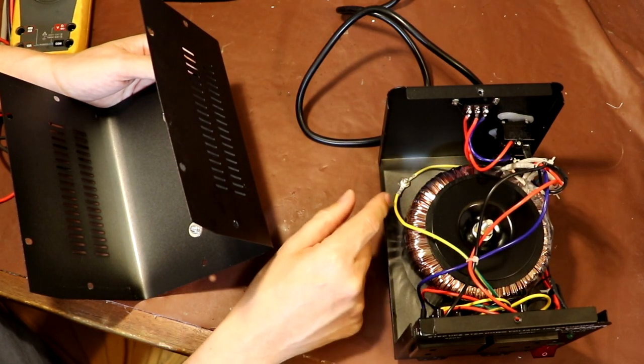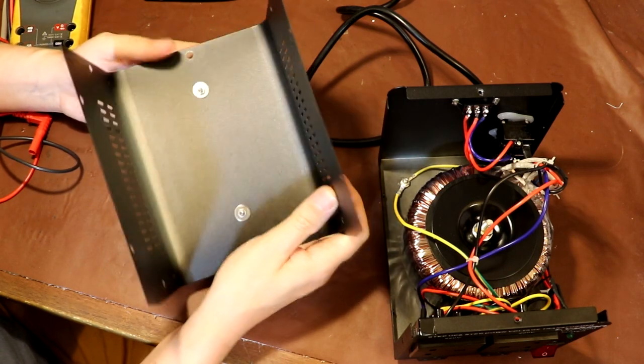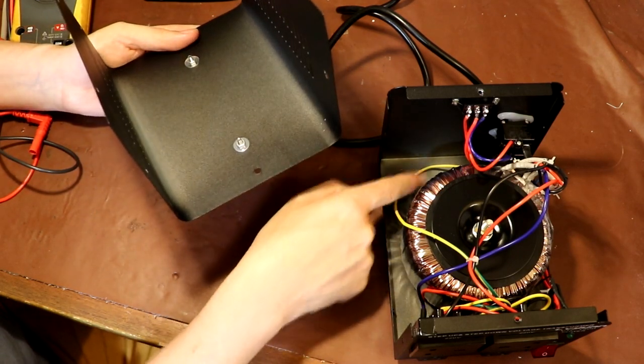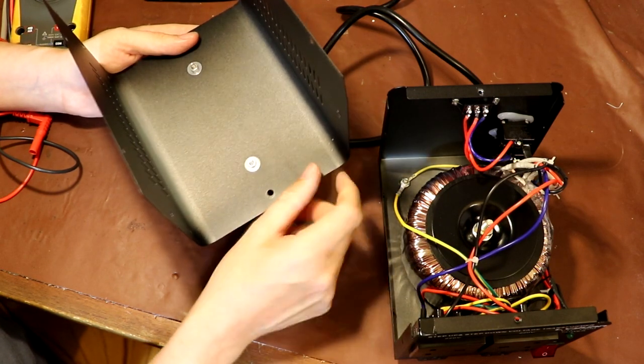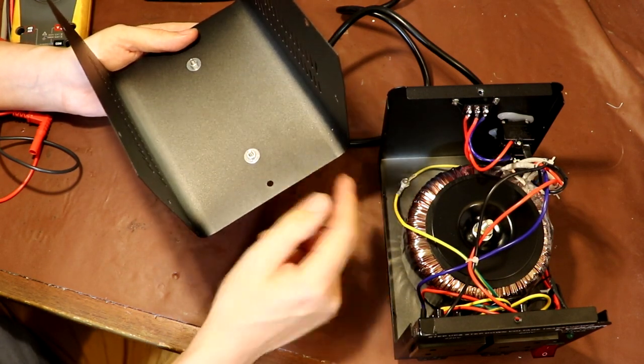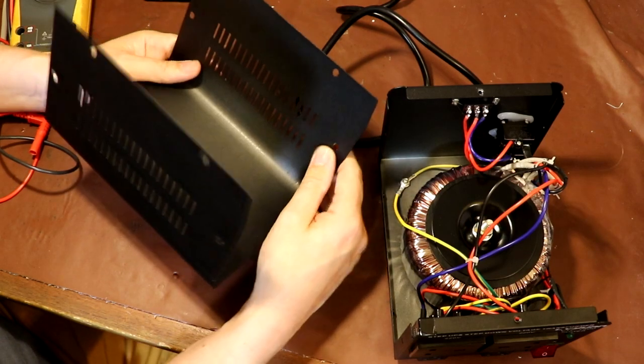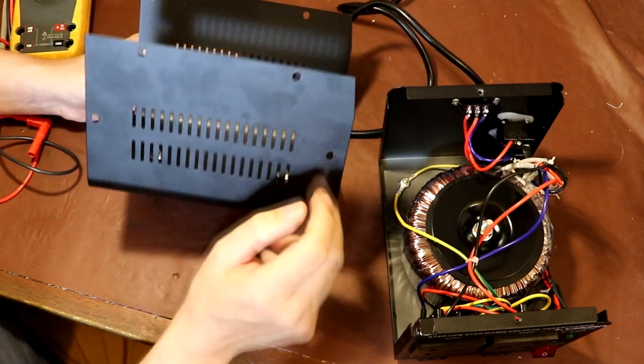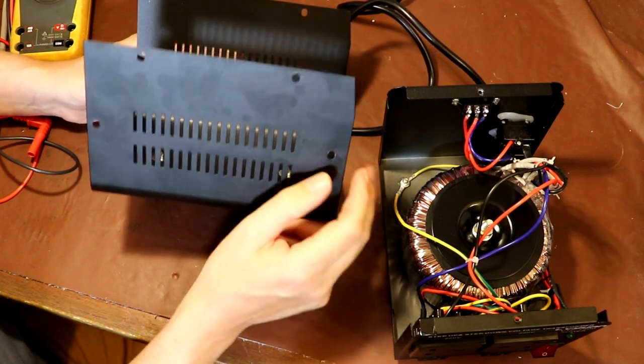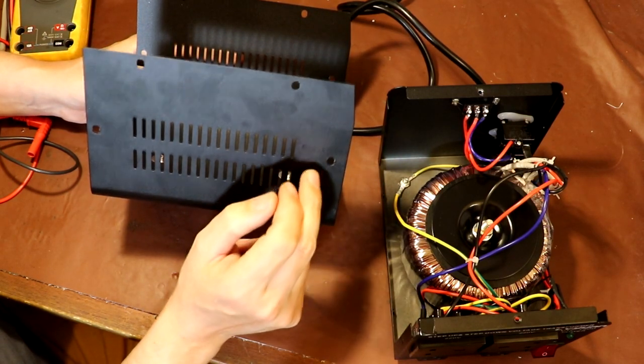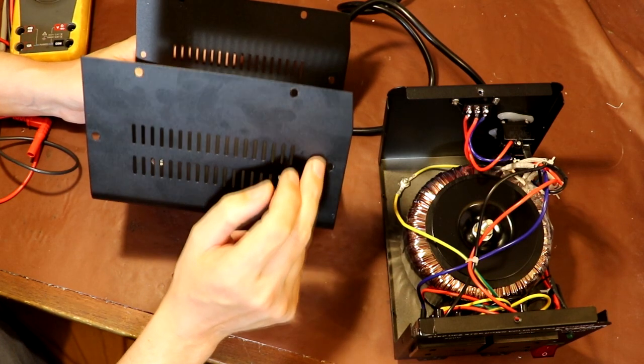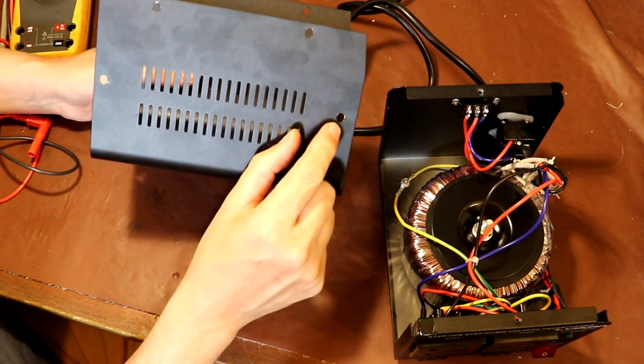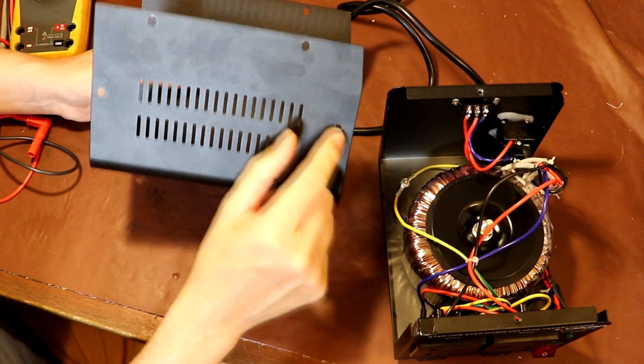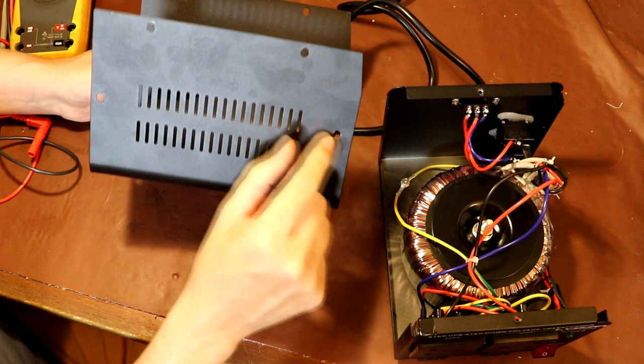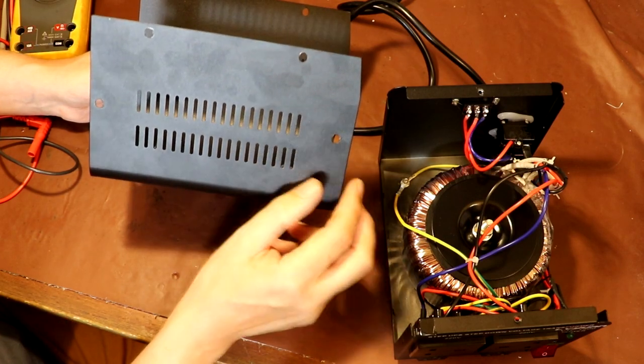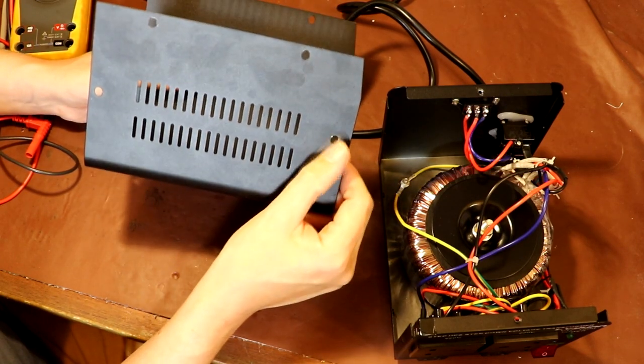then it goes off to the front sockets, but this is the top cover that I've just removed, and there's not actually any connection between here and the top cover. I would like to see an earth wire between this chassis point and the top cover, because at the moment it is actually relying on the screw fixings to provide the earthing for this top cover. That's not really a very good way of doing it, because as you can see these have actually got paint on them. Now as it happens, I can clearly see that the paint has been scratched off as the screws have entered into it, but that's more by luck than judgment.